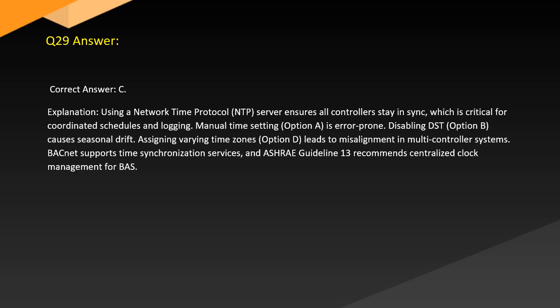Answer. Correct answer: C. Explanation. Using a network time protocol (NTP) server ensures all controllers stay in sync, which is critical for coordinated schedules and logging. Manual time setting, option A, is error-prone. Disabling DST, option B, causes seasonal drift. Assigning varying time zones, option D, leads to misalignment in multi-controller systems. BACnet supports time synchronization services, and ASHRAE guidelines recommend centralized clock management for BAS.